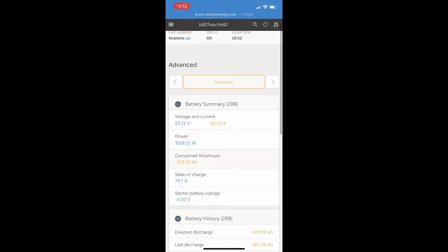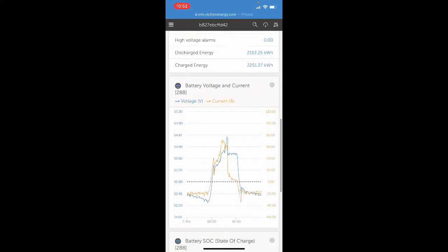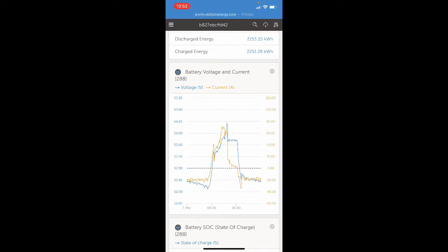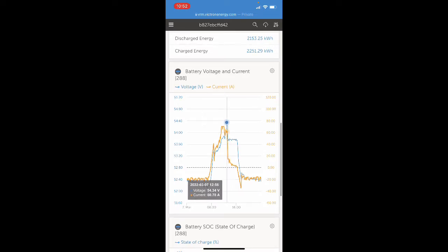The challenge I was facing is when the system is charging. You can see in blue the charge, and yellow is the current. The way it's set up, it hits a peak voltage around 54.5, then goes into float voltage, which I've now adjusted to around 53.7. That float voltage was causing a challenge where an individual cell out of the 16 would go high, and to protect the cell, the BigBattery BMS would disconnect charging. By disconnecting charging, the system would shutter and we'd lose power.